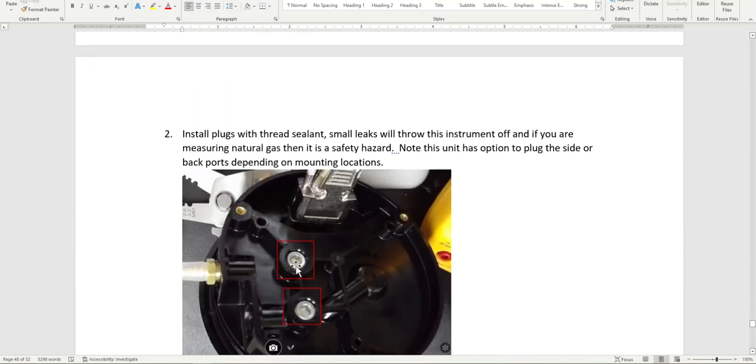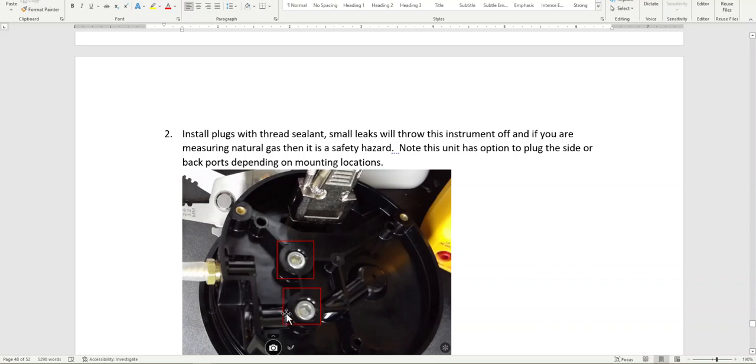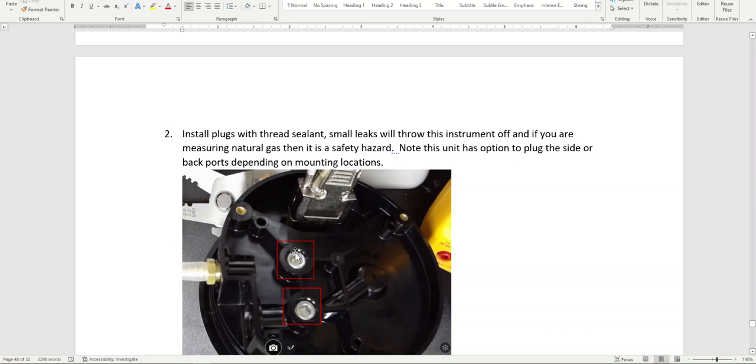Make sure you install the plugs. Know the configuration before you begin because you have these ports here. They are connected from here to here and you have to plug one of them. You must use thread sealant. Even earlier, I was just testing this and I did not use thread sealant. I could not get a good enough seal. I actually put my thumb over this entire thing and I had a leak and I could not run my sensor all the way up to 50 inches of water column using my pressure tester calibrator and my digital manometer gauge.